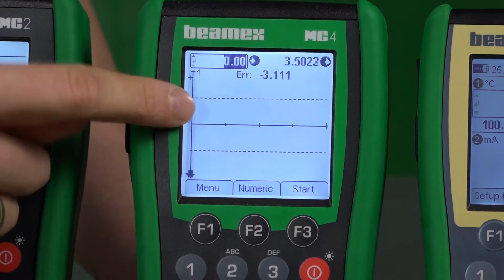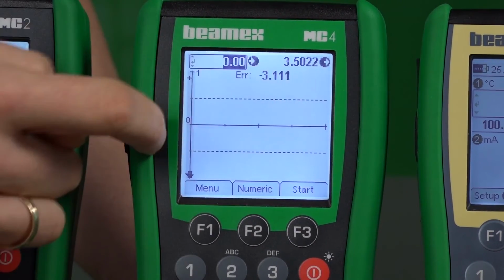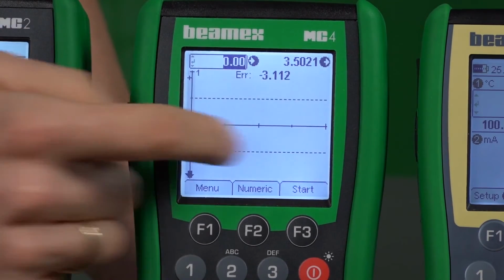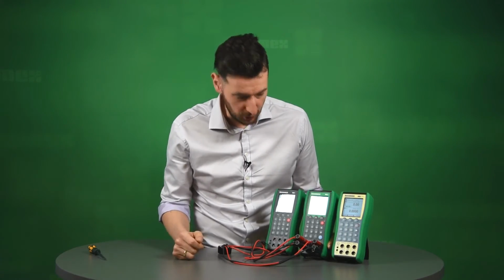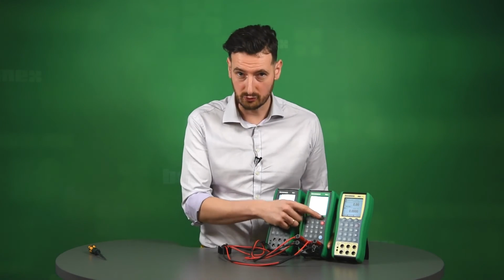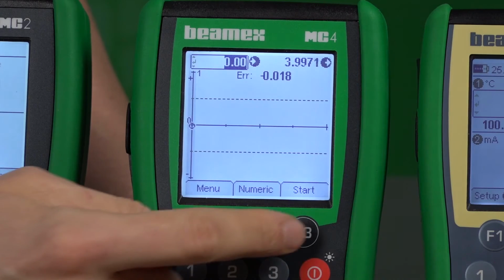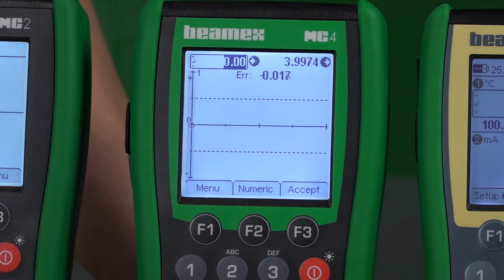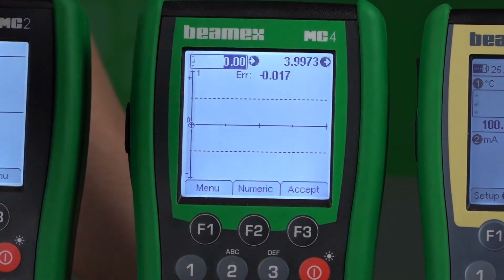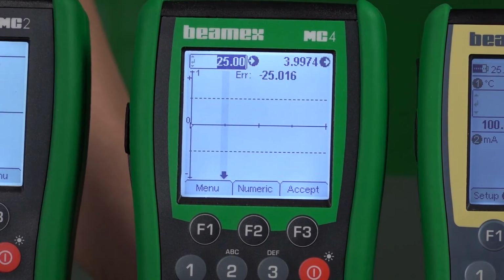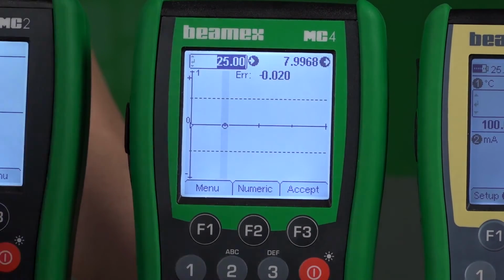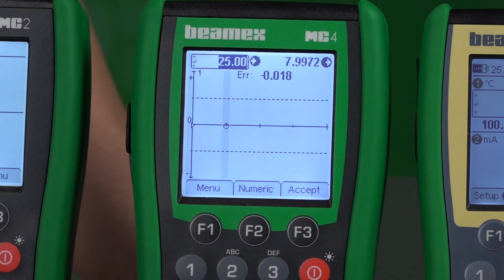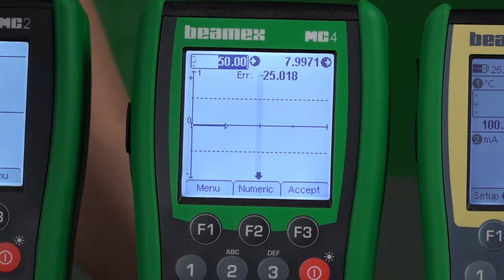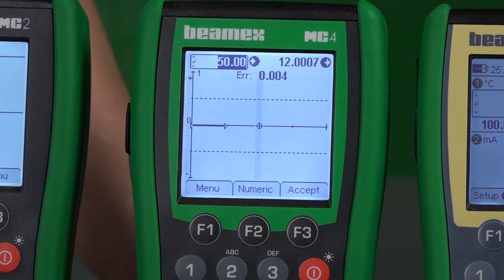You can see also here that we're going to have a graph. We're going to have the tolerance lines running here on the positive and negative. You can also see that if I just hit the start button, it's going to go 5 points up and 5 points down. So we're just going to do that now. It's going to have a set point delay of 7 seconds. So at each set point at 0 and 25 and 50 and so on, it's going to wait 5 to 7 seconds and it's going to accept those values after that time. It's just all about getting a stable reading.